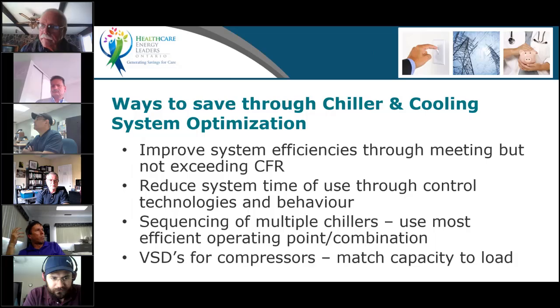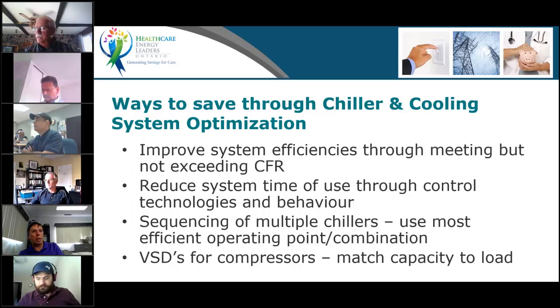Ways to save through optimization. Again, you need to know your CFR. What will be your cooling set point? Are you going to try to keep 21 degrees like we see sometimes in retail, or 20 degrees in retail and office buildings, which are really, really low set points? What is the dehumidification that you want to achieve, if you use dehumidification? Those are all things that need to be specified so you know what temperature chilled water you will need, what kind of reset you can use, when you can reset.